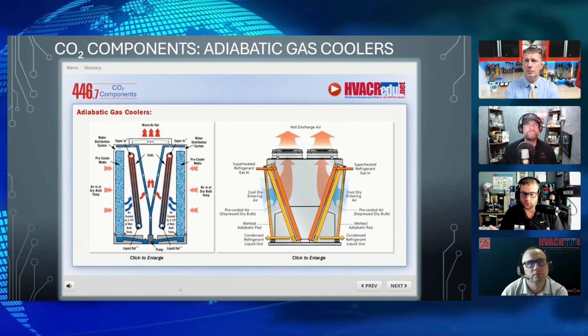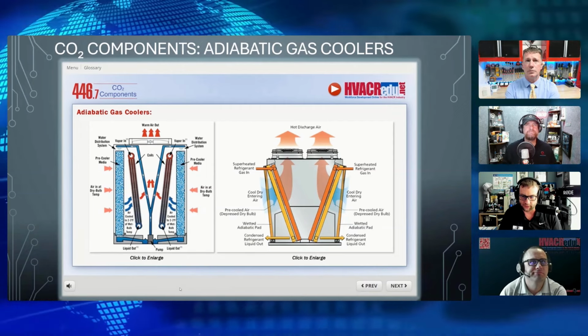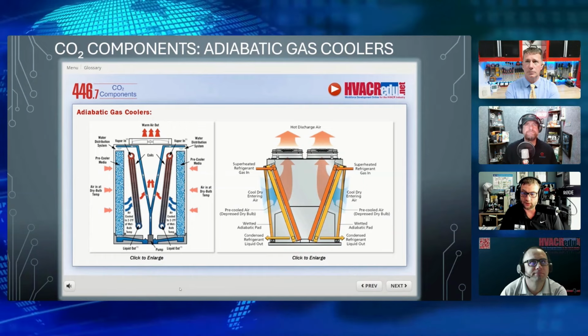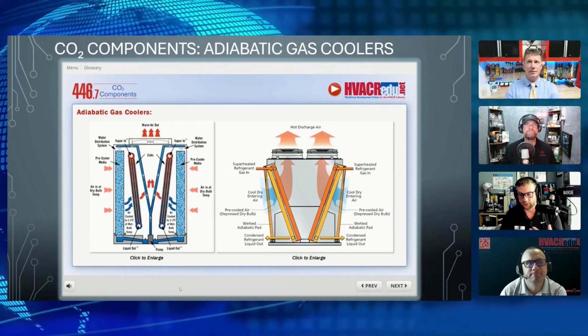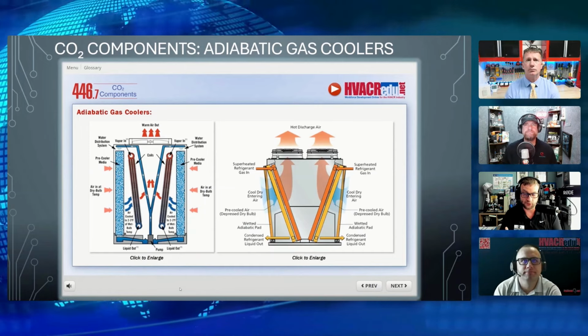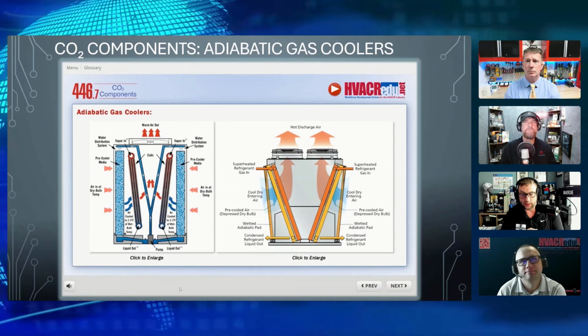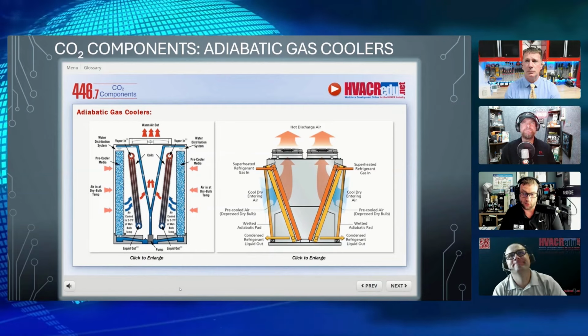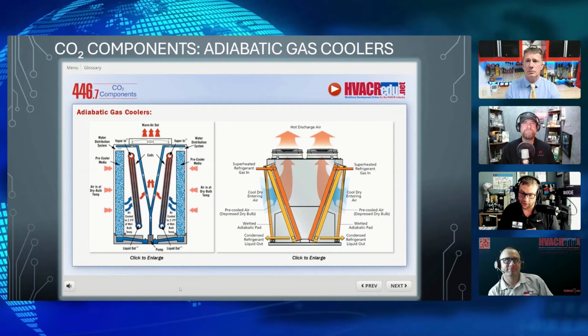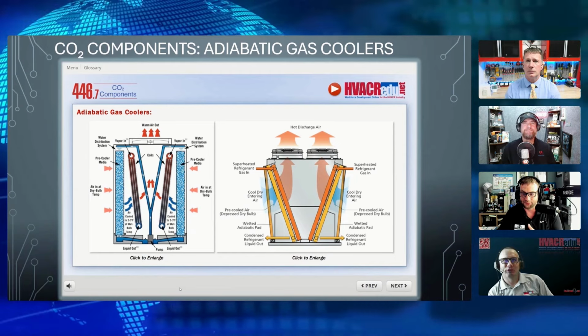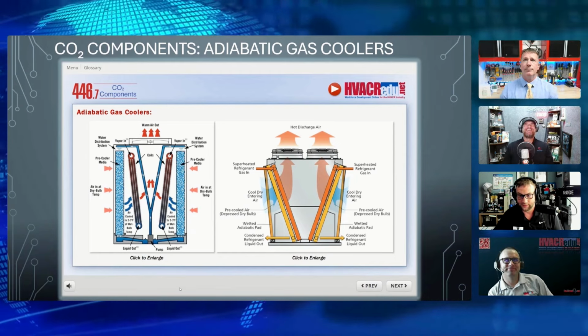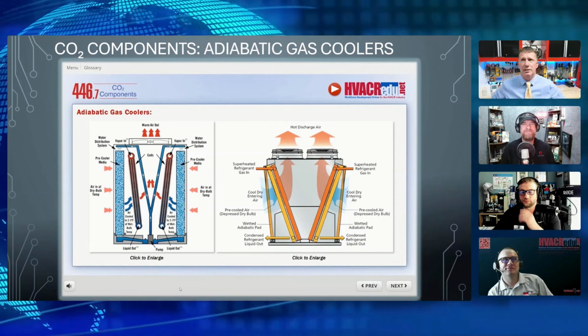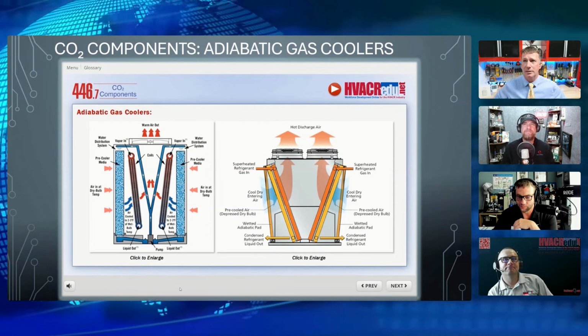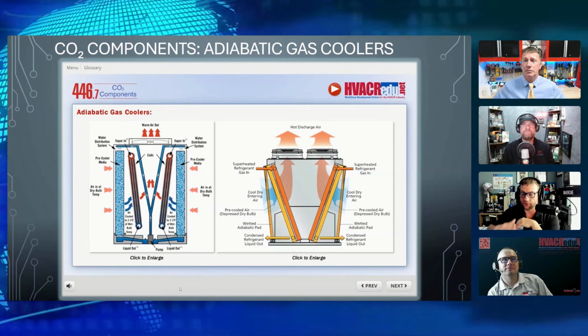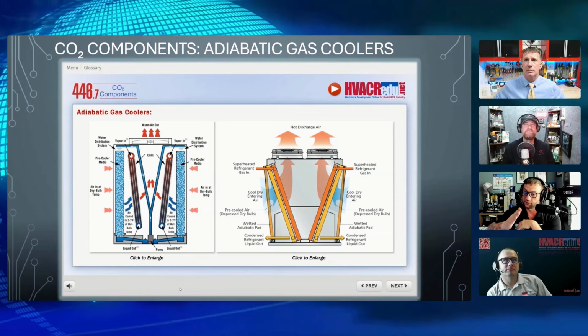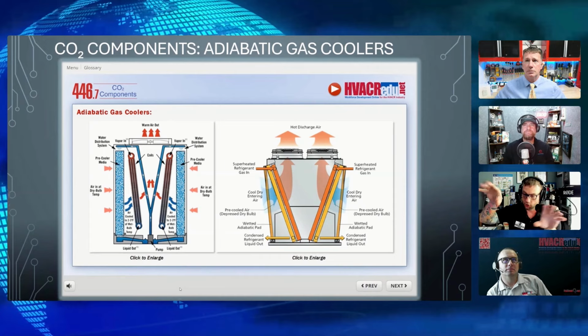Because think about it, with any kind of water cooling type device, it leaves particulates, right? You're evaporating that water, you're causing calcium chloride to build up, especially on these pads. So places that really need it, like Vegas, might have really bad water. The more you evaporate off, the more particulates, and it looks like an old trucker stop coffee pot in the bottom. So we're actually going to use enthalpy to calculate variable speeds for pumps in these scenarios. Yes, you could do that, or maybe just a flow valve, like a Belimo valve, to mitigate how much water we're actually putting across those pads.